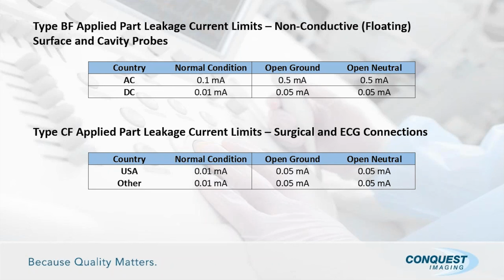Then they have the type CF, which is cardiac floating, and these are much more stringent conditions because the patient, when they're using it, obviously can't report any discomfort because they're under anesthesiology. So we have to be really careful about this, and what you want to do is measure the normal condition, the open ground condition, and the open neutral condition. Again, be careful that you don't do that with the system on. And it gives you the conditions for the United States and other. Notice they're the same, but I do like to point out that there are differences between us and the international, some of the conditions.